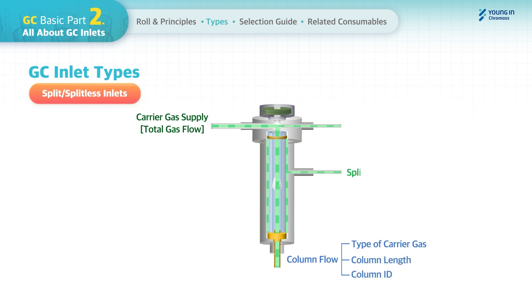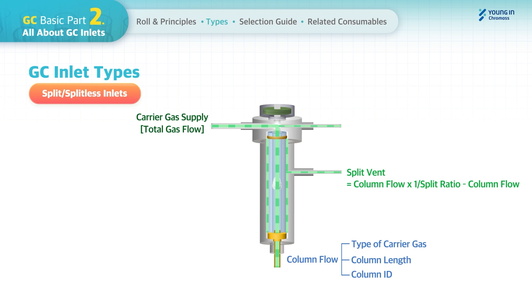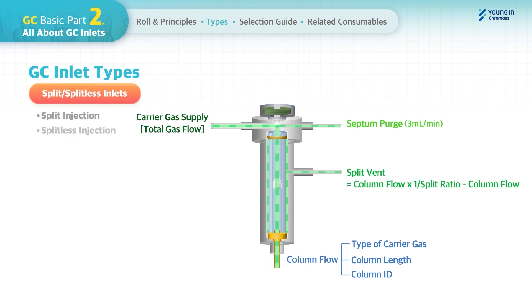The column flow is determined by the type of carrier gas, column length, and column ID. Split vent flow is calculated from the column flow and split ratio, which varies depending on sample concentration and column ID. The septum purge sweeps away septum scraps to remove potential contaminants and is usually set at 3 mL/min.